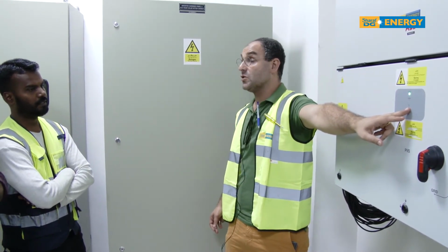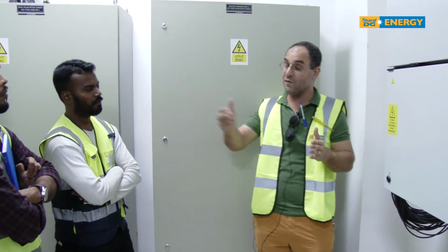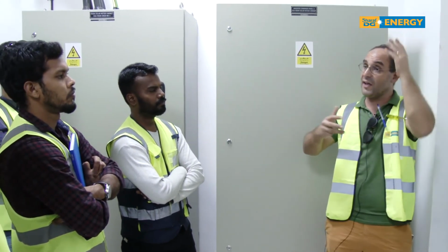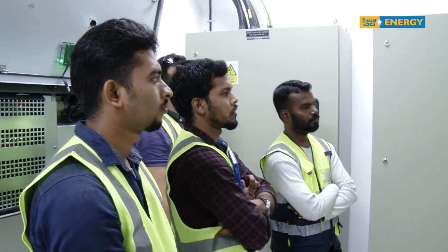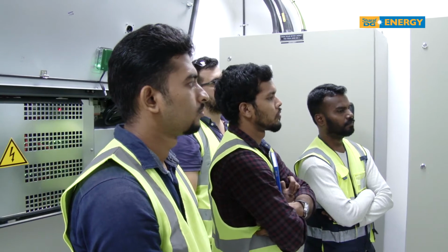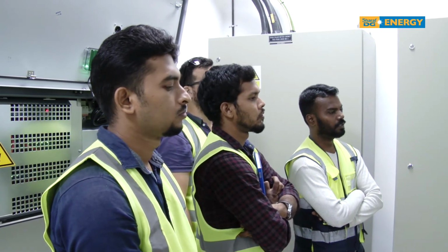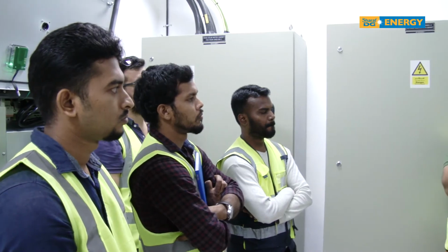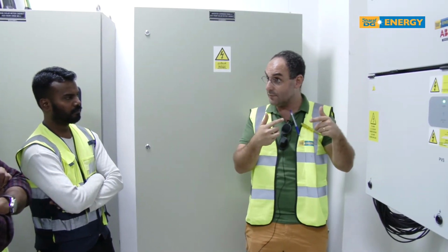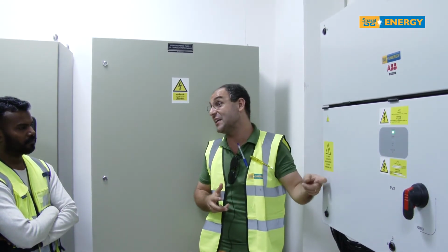Because, for example, over time the connectors on the roof may become faulty, or something could happen, and this could originate a ground fault. So in the early morning, the inverter makes an insulation resistance test and registers that value. But throughout the day, to make sure the insulation is still guaranteed and people are safe, the inverter does an earth leakage test, and does that every single moment.